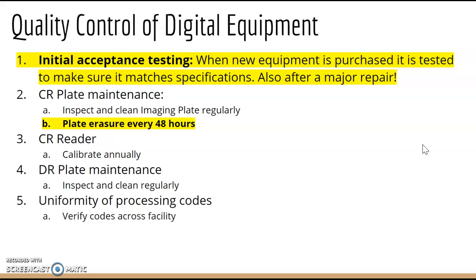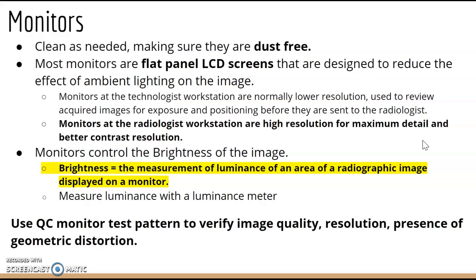For digital equipment QC, there is always initial acceptance testing when new equipment is purchased to verify it matches specifications. Physics will also perform testing after a major repair — for example, if a tube is replaced, it must pass acceptance testing before use on a patient. CR plate maintenance includes inspecting and cleaning imaging plates regularly and erasing cassettes every 48 hours.